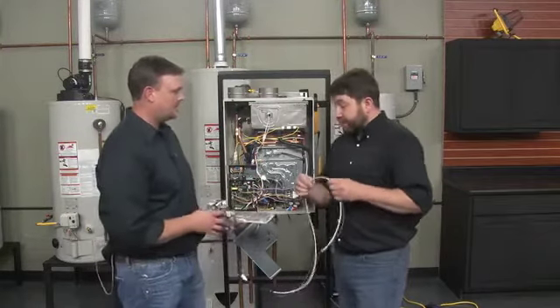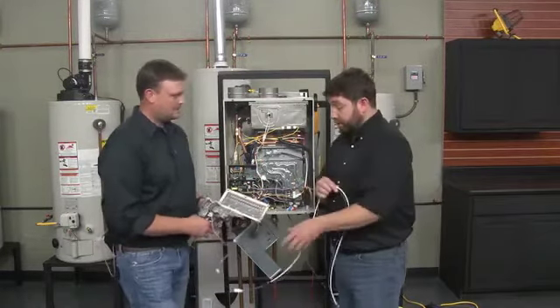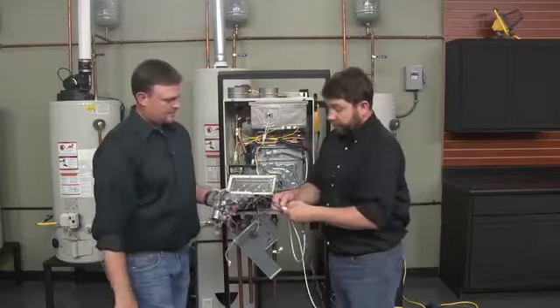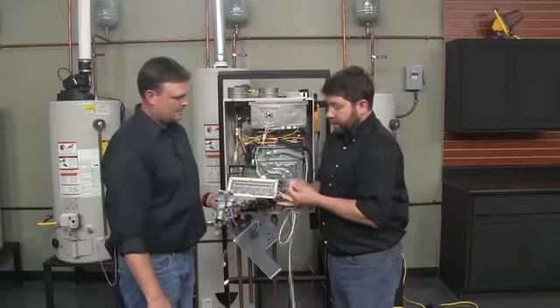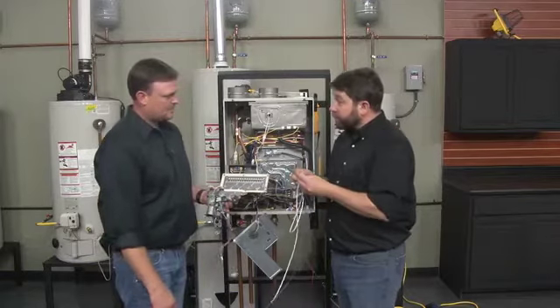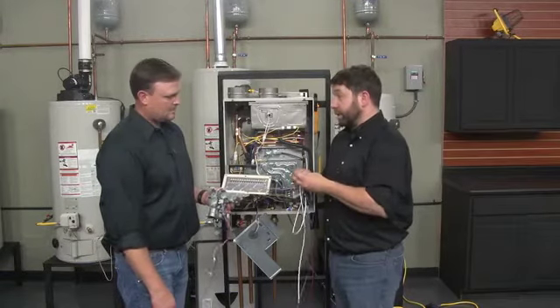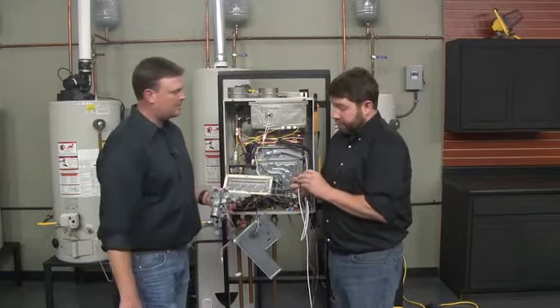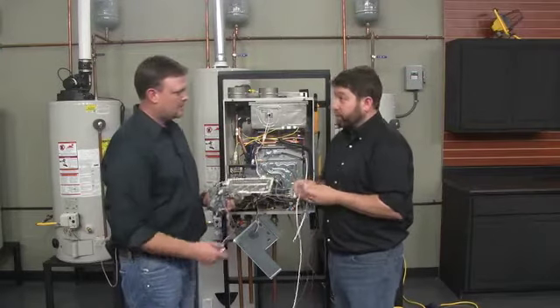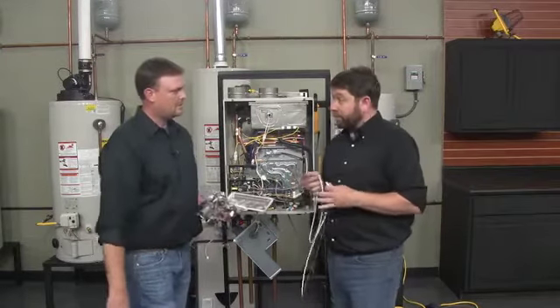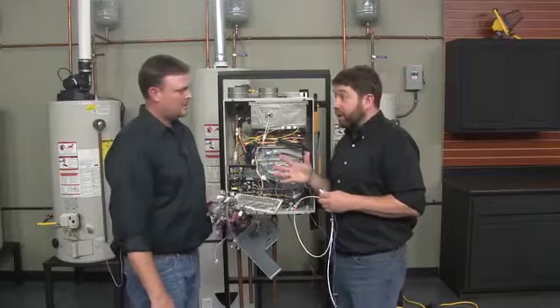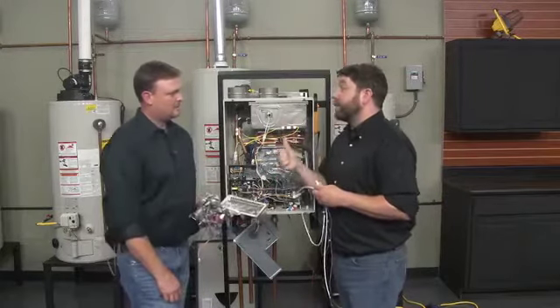Anytime that this safety is opened up, you can check it. It unplugs from the rest of the string, and you can check between those contacts. Now, don't get too aggressive when you're sticking meter probes in there because we don't want to damage this connection. We're just looking for continuity. If there's no continuity through this, you have to pull the heat exchanger all the way out because we want to see where that heat came from.